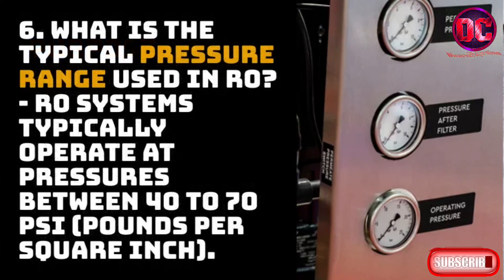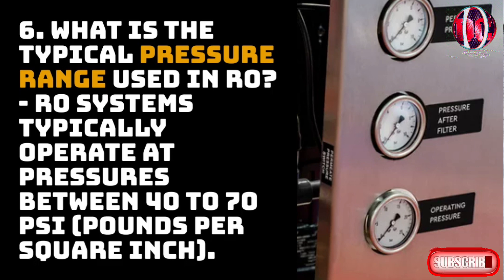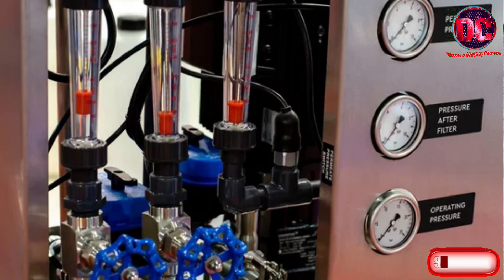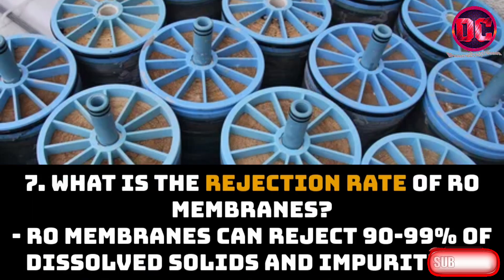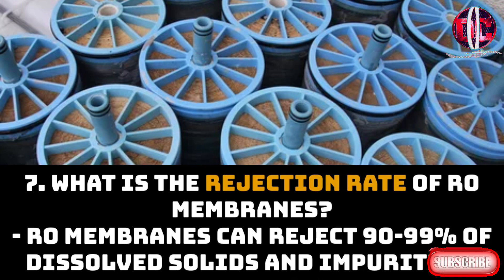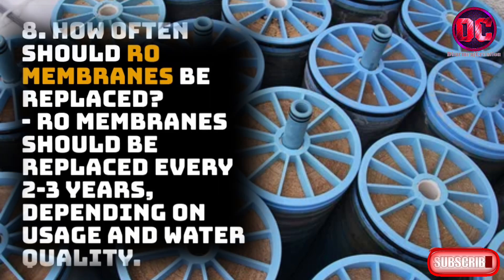6. What is the typical pressure range used in RO? RO systems typically operate at pressures between 40 to 70 pounds per square inch (PSI). 7. What is the rejection rate of RO membranes? RO membranes can reject 90 to 99% of dissolved solids and impurities. 8. How often should RO membranes be replaced? RO membranes should be replaced every 2 to 3 years, depending on usage and water quality.